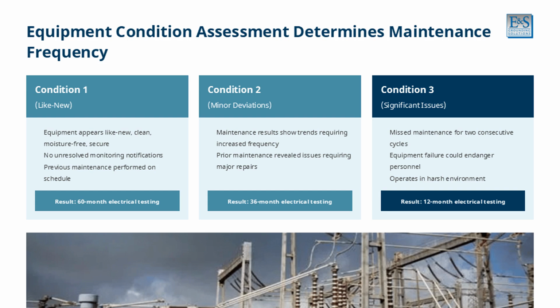Condition 2 indicates minor deviations. Maintenance results showing trends requiring increased frequency, or prior maintenance revealing issues requiring major repairs. This results in moderate intervals, such as 36-month electrical testing. Condition 3 signals significant issues: missed maintenance for 2 consecutive cycles, equipment failure that could endanger personnel, or operation in harsh environments. This requires the shortest intervals, such as 12-month electrical testing.